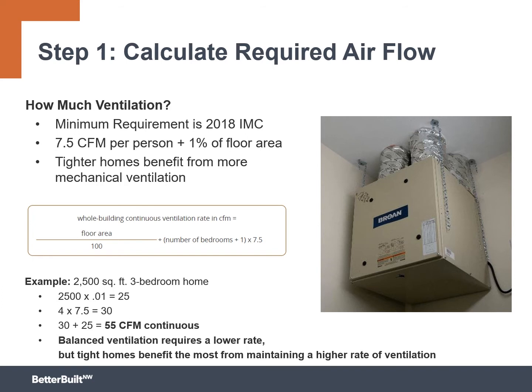How much ventilation do we need in Washington State's energy and mechanical codes? So we need 7.5 cubic feet per minute per person, plus 1% of the floor area. That's the minimum. Tighter homes, if you start taking some of those energy credits from table 406.3 for tighter construction, you may benefit from putting in even more ventilation than the minimum. The tighter the home, the better it benefits with more ventilation, particularly when it's balanced.